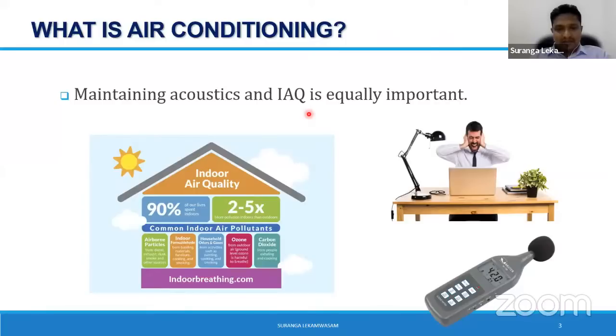There are various ways that you can maintain this IAQ level. Let's say you have airborne particles like dust, smoke, hydrocarbons, etc., you can do simple filtration and remove them. But there are certain parameters which you cannot physically filter. For example, carbon dioxide. We continue to expel carbon dioxide, and finally the level of carbon dioxide, the ppm level, continues to increase within the ambient. So how do we control carbon dioxide? The only option is adding fresh air. So to maintain the IAQ level, filtration as well as fresh air is essential for you to look at.